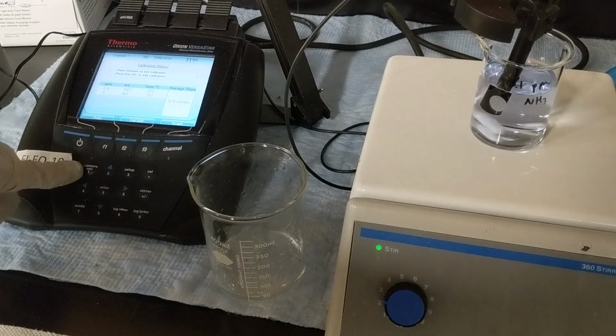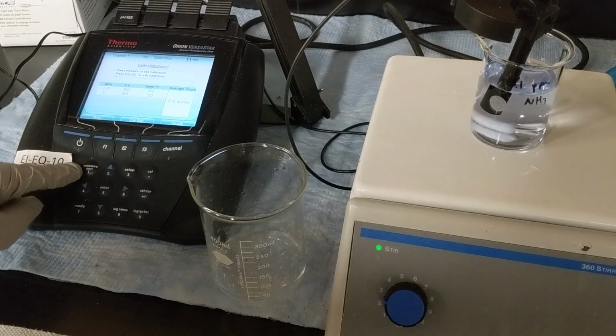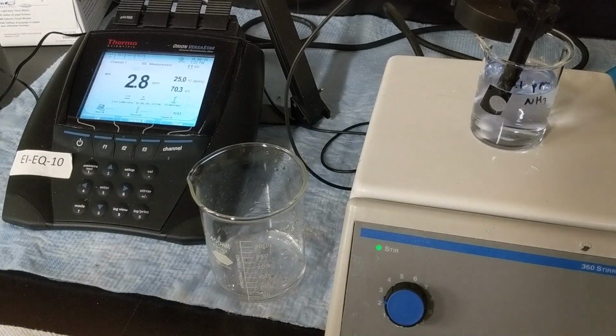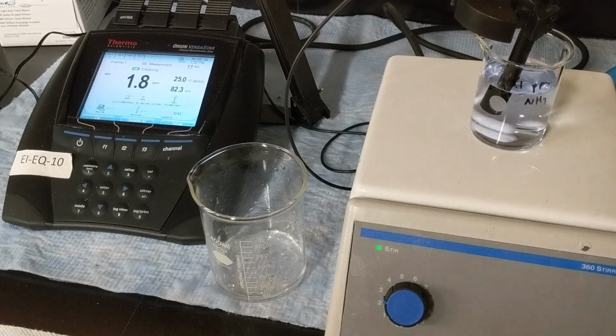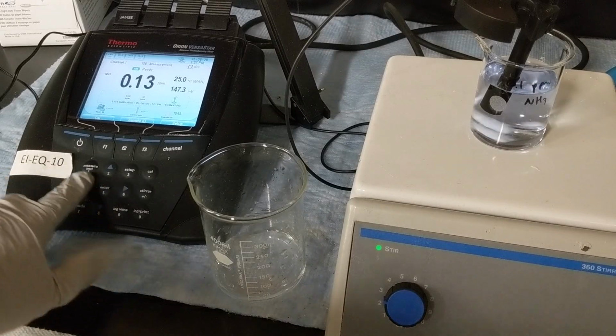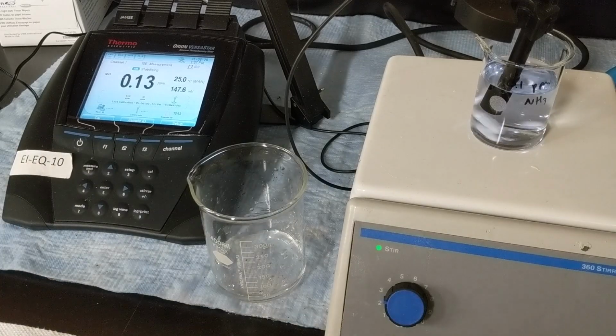And now the 1 button also acts as the measure button. So this is how we can get to just regular measurement. And so my hope is that this comes in at a measurement near 0.1 part per million. You can see it's decreasing from the 10 where it was, but it will take a little while before it gets down to where it should be. Okay, so it has stopped at 0.13 part per million. I'm just going to hit the measure button again, and if the next measurement is also 0.13 part per million, that is what I would record as the final measurement.